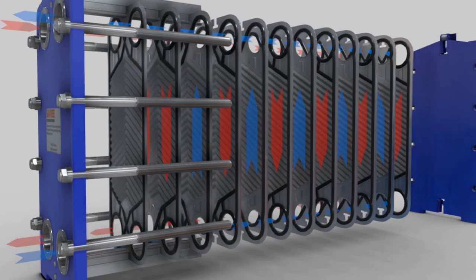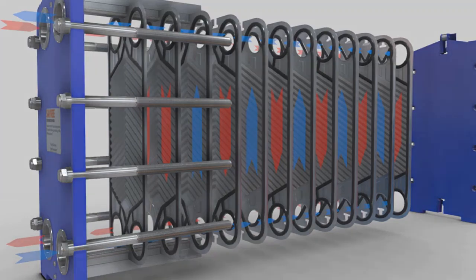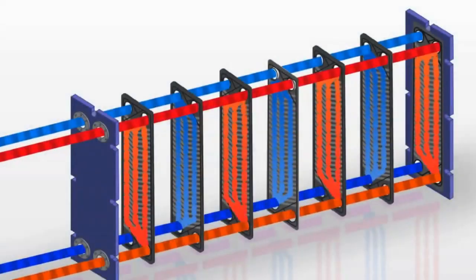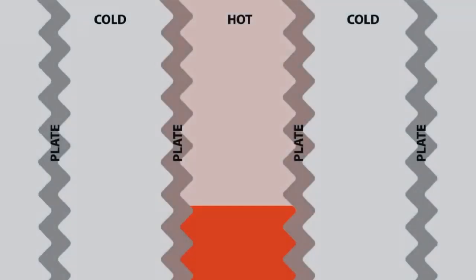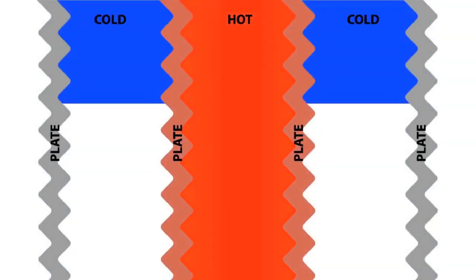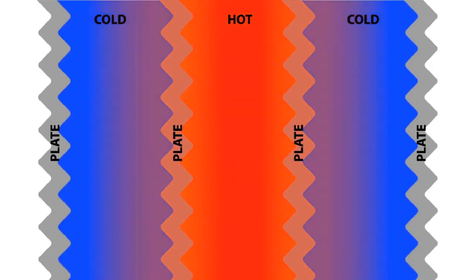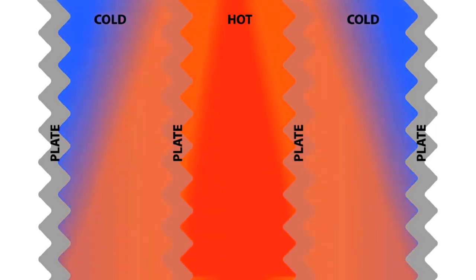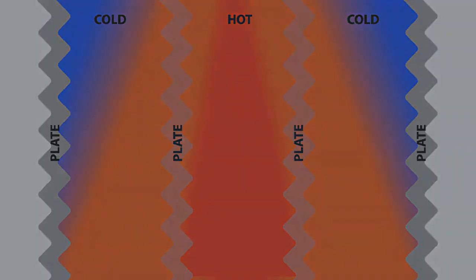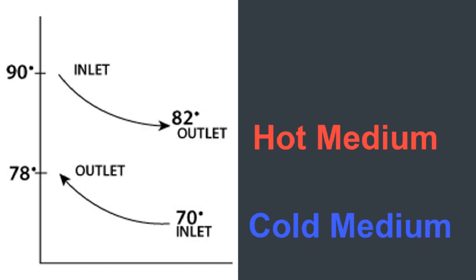Notice that the two flowing mediums are always adjacent to each other throughout the heat exchanger. The flowing mediums thus have a hot-cold flow pattern as they flow through the heat exchanger. They are completely separated from each other by the gaskets and plates, and they do not mix. Due to the close proximity of the flowing mediums, heat is exchanged between them. The hot medium heats up the plate, and the plate passes some of this heat to the cold flowing medium. Thus the hot medium temperature decreases, whilst the cold medium temperature increases.